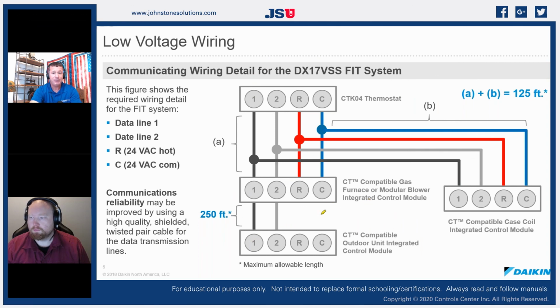Here's the thing that we see fairly often as well, because remember, going from that indoor unit to the outdoor unit, we have no common, which means we rely on ground, right? Our outdoor unit has to be properly grounded. And we've had instances where we've had outdoor units that had lugs inside of the disconnect that had rusty screw terminals, because sometimes we'll have that aluminum block that our ground wires connect into, but it'll have a steel set screw. So we've had those steel set screws be rusted to the point where we weren't making proper ground.